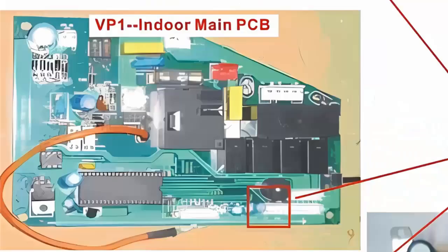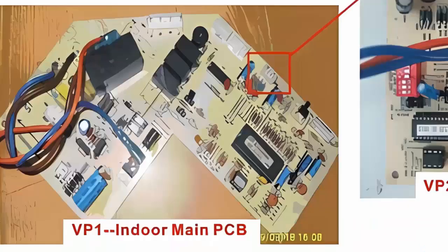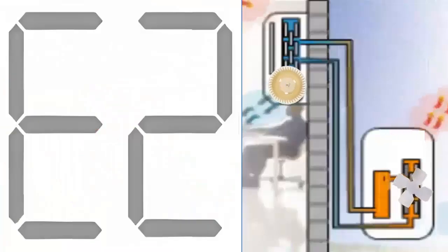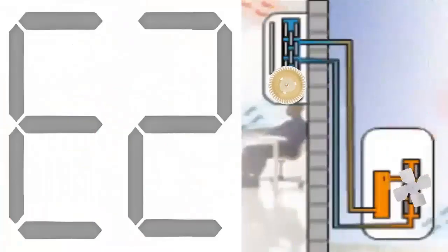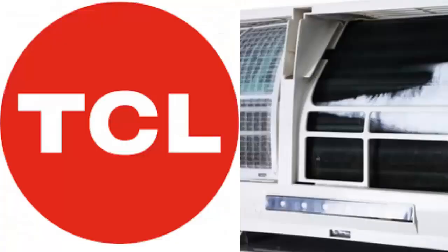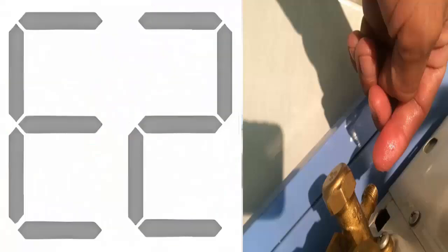7. If replacing the coil sensor does not resolve the error, it is highly likely that the problem is within the indoor unit's electronic board. In such cases, it is recommended to perform a visual inspection of the electronic board for any abnormalities. 8. If the error disappears, but the unit occasionally experiences freezing after performing the above steps, the system may require a refrigerant gas recharge.